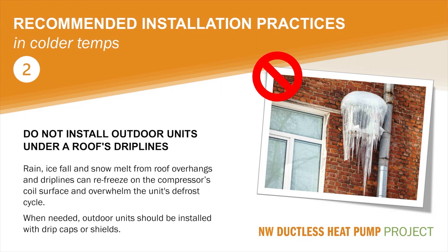If this is not possible, install a drip cap or shield to keep the drip line off of the outdoor unit. It's worth noting that if an outdoor unit becomes covered with ice and the defrost cycle is unable to clear it, system performance will suffer. This means occupants will not be comfortable because the heat pump will not be able to produce enough heat, and the system will likely be using more energy to try to compensate.